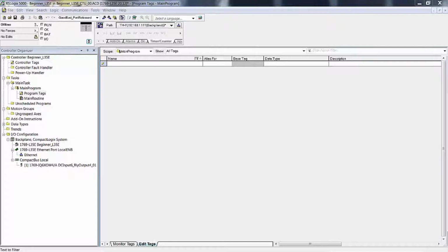Also, regarding timer data types, other than the reset instruction, an instance of a timer instruction such as TON, TOF, or an RTO is executed against a unique instance of a timer data type for each instance of a timer instruction. Counter instructions such as count up and count down can both execute against a single instance for both instructions. In other words, with TONs, RTOs, TOFs, you normally would not execute two of those instruction types against one single instance of a timer data type.